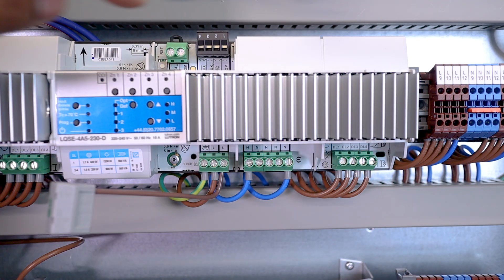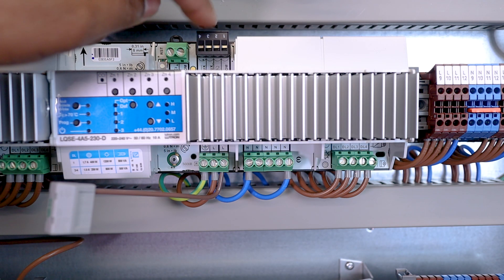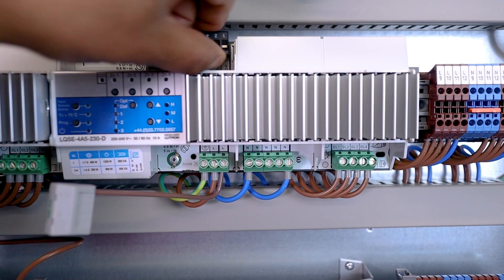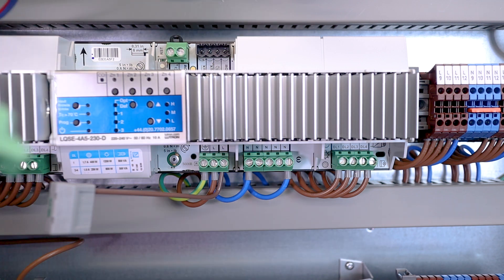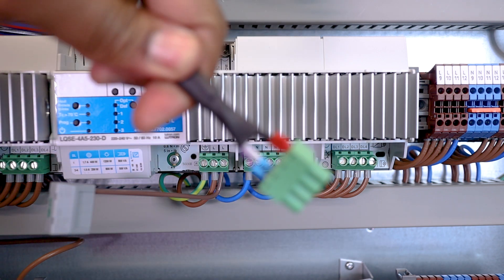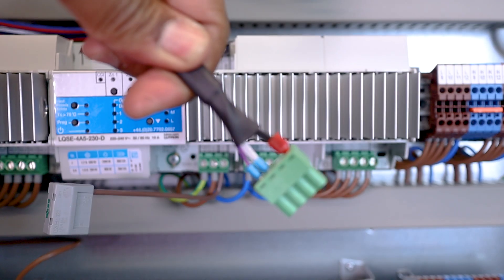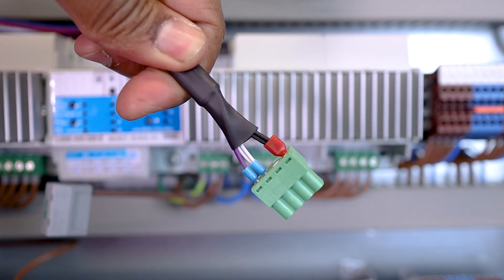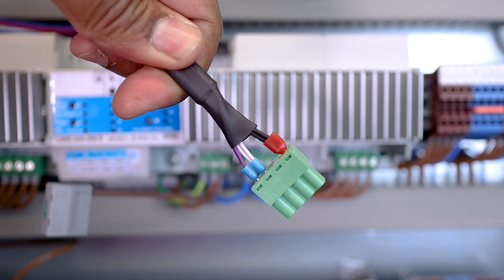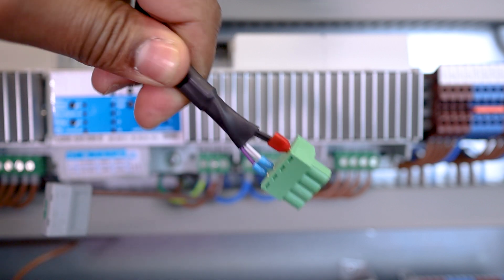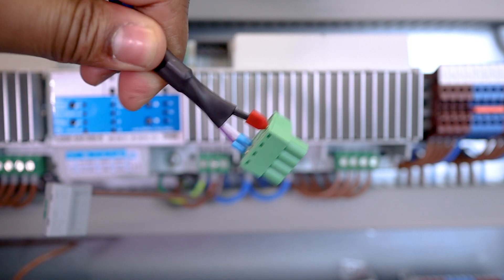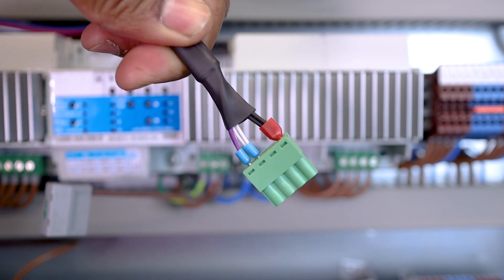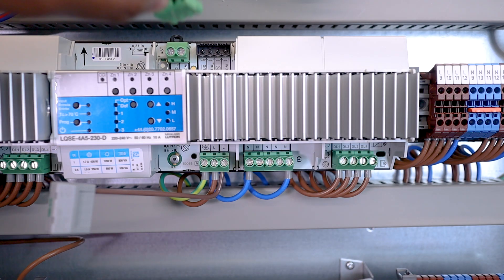Now, I just need to remove the communication connector here, and plug the one that came ready with that pre-wired future automation panel. And as you can see, pin number two on the connector is not wired, which is how we should be between the Lutron modules. Great!